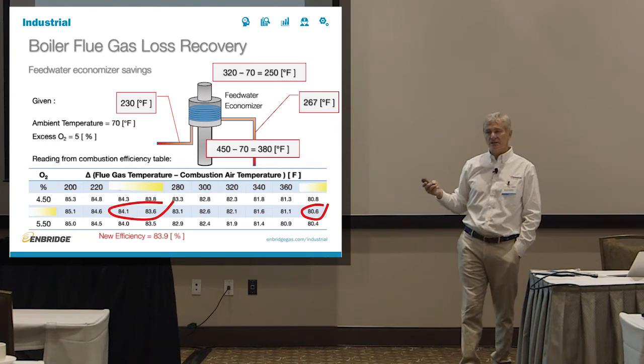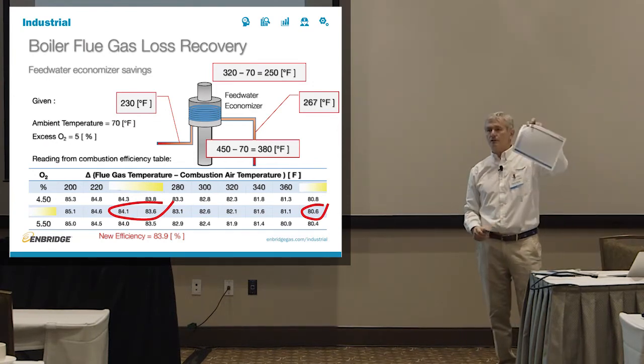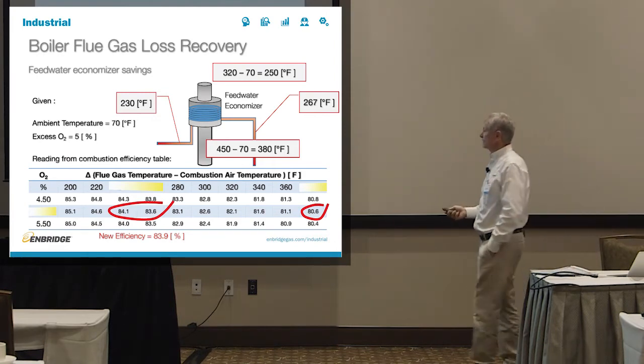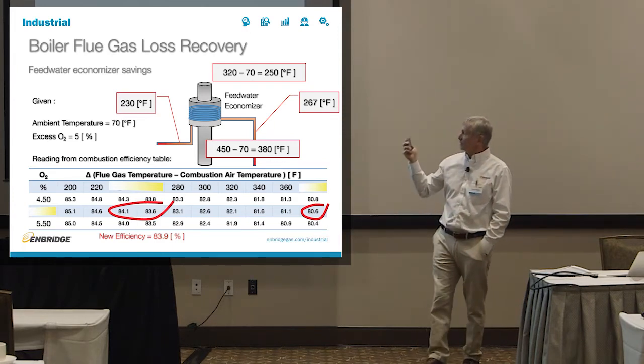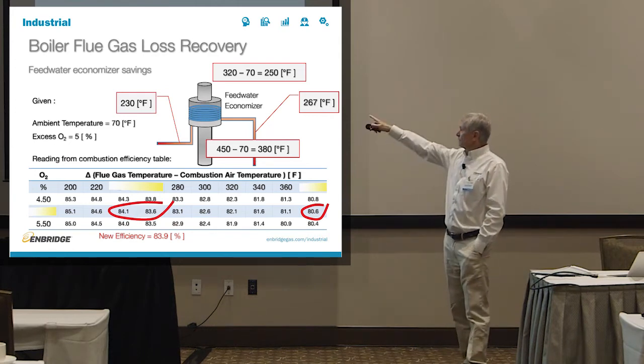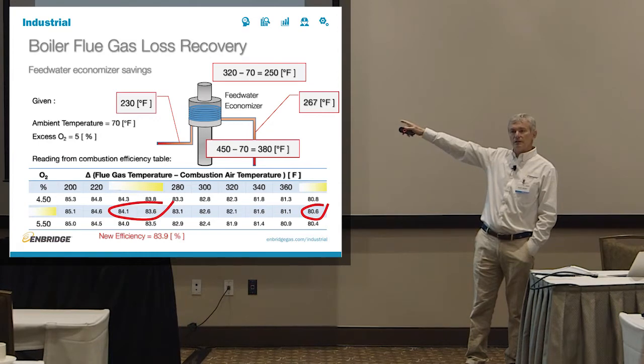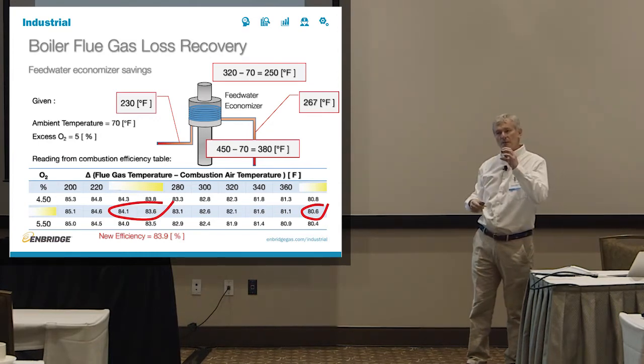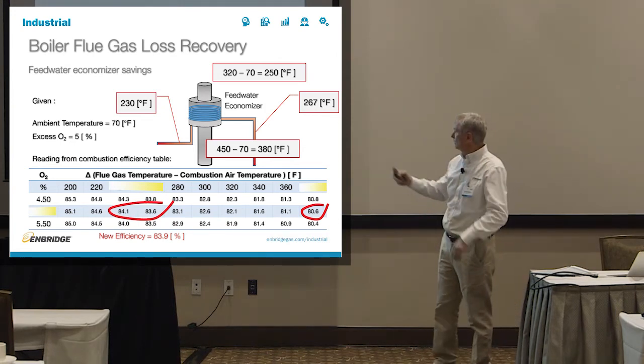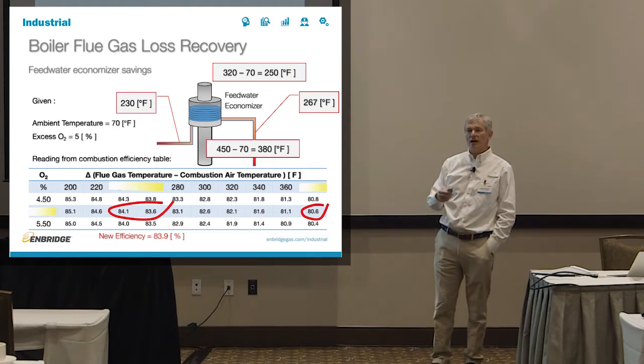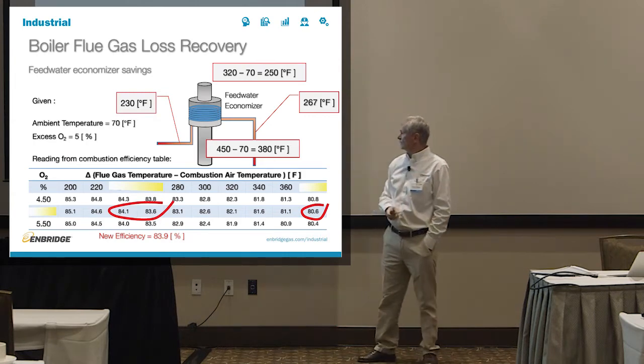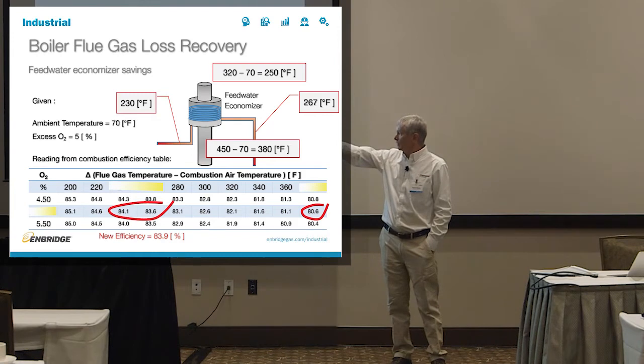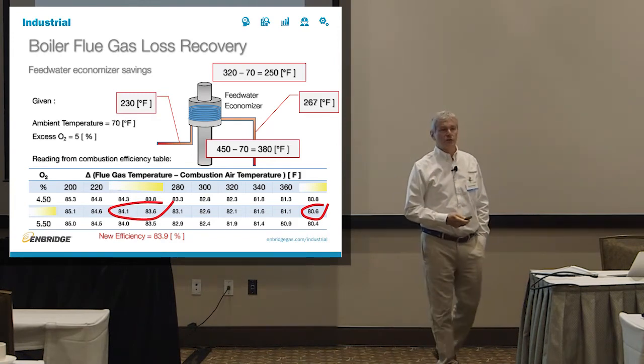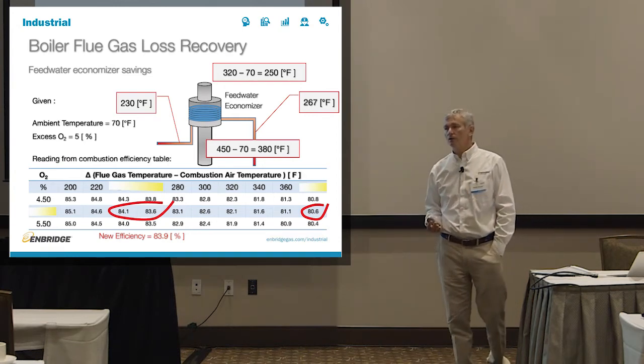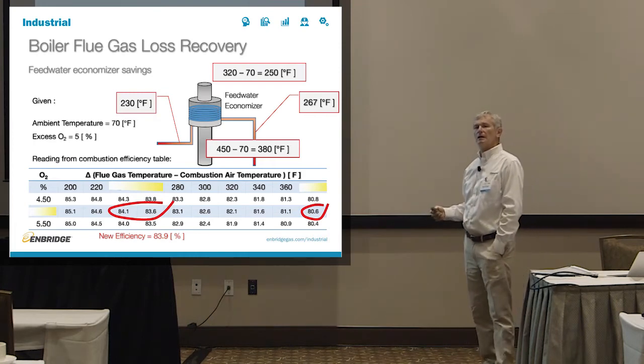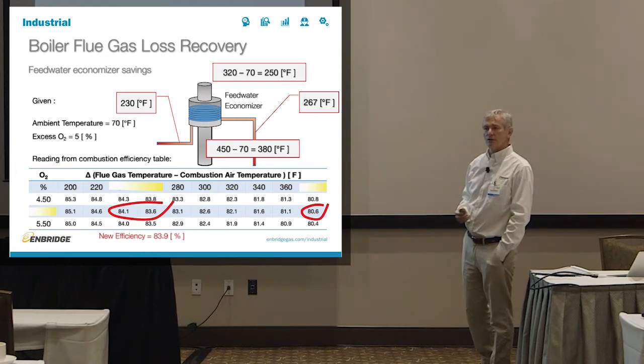And here's how you calculate. This is as simple as it gets. You will have a natural gas combustion percentage chart in your book, so you can easily find these things. Down here is an excerpt from it. Let's say you have 5% excess oxygen and 450 degrees F exhaust gas before the feed water economizer. Minus 70 degrees, which is the ambient temperature. You always look at the net temperature, rather than just the fixed temperature of the boiler. So that puts you at a 380 degrees F exhaust temperature above ambient, which puts you right here, 380 degrees F. On the other axis, 5% oxygen puts you at 80.6% efficiency. It's as simple as that. That's how you calculate the efficiency of the boiler. As long as you know the temperature of the exhaust flue gases and your oxygen level, that's all you need to calculate the efficiency.